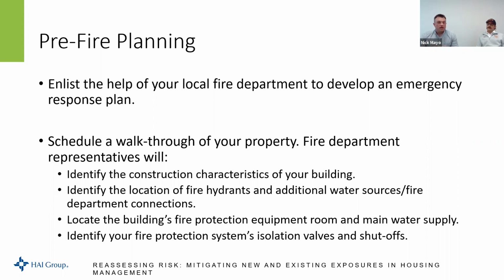Walking through the building, if there is any fire protection system, we'll take a mental note of isolation valves and shutoffs, because as a fire department, which we'll talk about later on, being able to close an isolation valve if there is an activated sprinkler head makes our job a lot easier if the fire is under control. So in saying that, Paul, if a building owner, property management company, or housing authority wants to contact a fire marshal's office to schedule a walkthrough, what's some information that you would need, or how would you approach a request coming from a person?